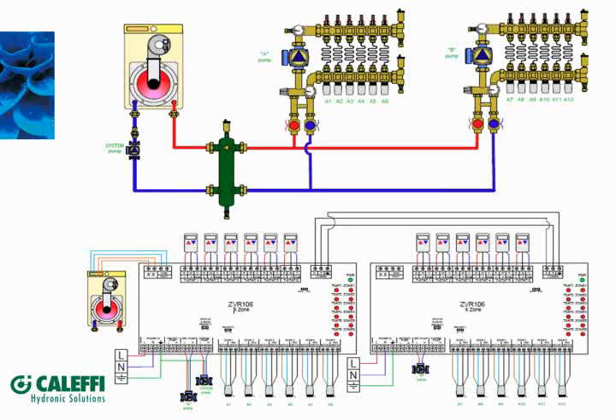But another question here, is this a good one? If you have zone valves without end switches, sure, you can do that. You just need to put a jumper on the end switch contacts. Then as soon as the call for heat comes, it'll deliver 24 volts here and fire the pumps as soon as that happens, because we usually wait till the end switch is closed, but if there is no end switch, you can just jumper it closed. Yeah, and then on a thermoelectric, of course, it'll take that time to open, but it shouldn't be a problem.